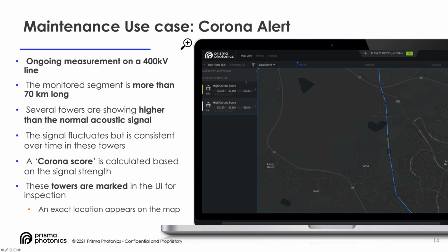We did a measurement over the 400 kilovolt line, monitoring a segment of more than 70 kilometers, with more than 100 towers, even close to 200. We found that not all towers get the same scoring, so we can pinpoint the few specific towers that are more problematic than others. This enables precise and cost-effective predictive maintenance, because we know precisely where problems start to evolve, which tower needs attention, and when preventive maintenance action items are needed.